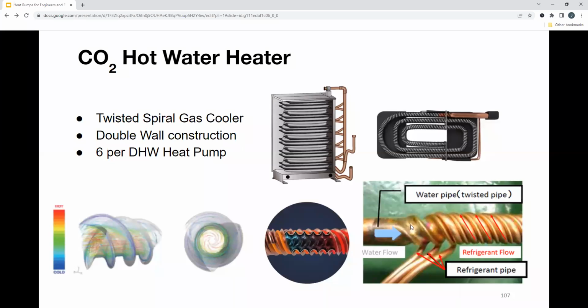And this is kind of what the gas cooler looks like. It is a twisted spiral gas cooler. What's cool about this is you have counterflow, so you have your water pipe going this way, then you have refrigerant piping wrapped around going this way. Because that refrigerant pipe is wrapped around, it increases the surface area, which increases the heat transfer in this pipe, right? So it's double wall construction, and you have basically 6 of these coils stacked on top of each other to make up that gas cooler, to provide hot water to these storage tanks.